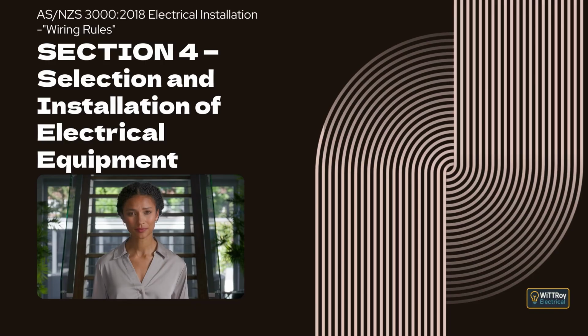Clause 4.16, Electrical equipment containing liquid dielectrics. This clause explains the safety precautions required where electrical equipment contains significant amounts of flammable liquid, such as oil-filled transformers or capacitors, so that burning liquid and combustion products like flame, smoke, or toxic gases do not spread to other parts of the premises. Clause 4.16.1 General. Wherever electrical equipment contains flammable liquid in significant quantity, precautions must be taken to prevent the spread of burning liquid and the products of combustion to other areas of the building or site. Clause 4.16.2 Liquid dielectrics having a flash point not exceeding 250 degrees Celsius.